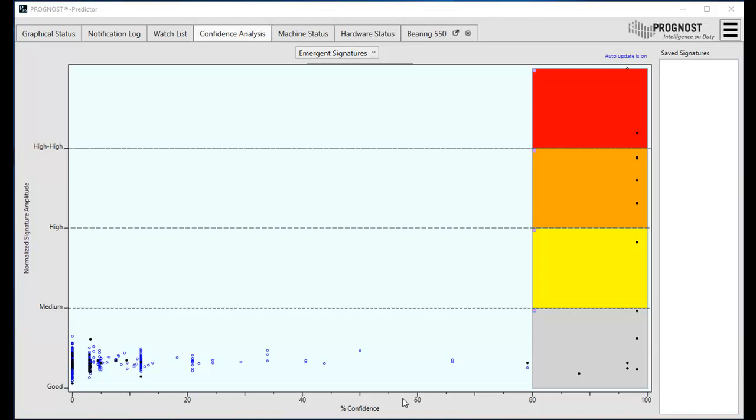There are three types of signatures: emergent, persistent, and direct. Rolling element bearing signatures are emergent signatures because the spectral lines are not present when the bearing is in good condition and begin to emerge from the spectrum as a fault develops. Some other signatures, such as imbalance or gear mesh, are persistent signatures, since even when the component is in an acceptable condition, these spectral lines are present.